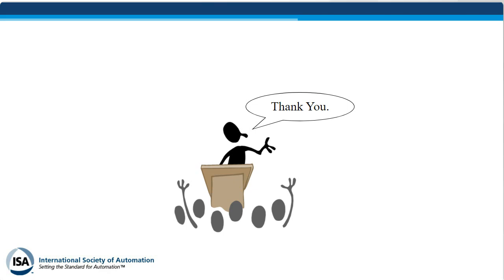But one of the key things, if I'm at a company that has not embraced alarm management, is to start looking at your standing alarms, your chattering alarms, and what I call your bad actor list, and start working.